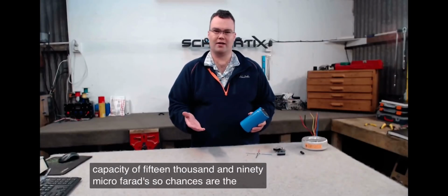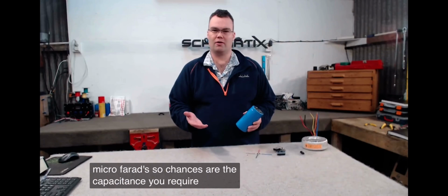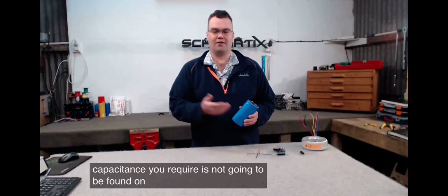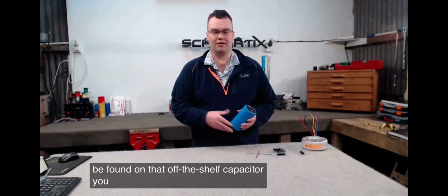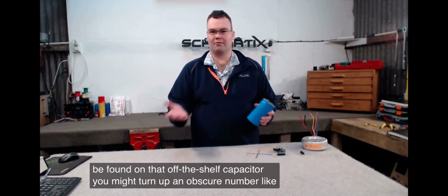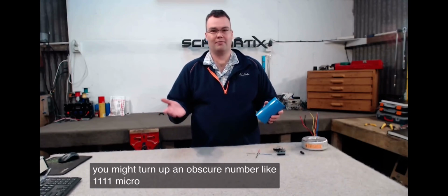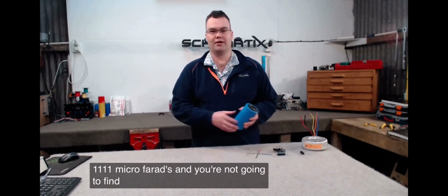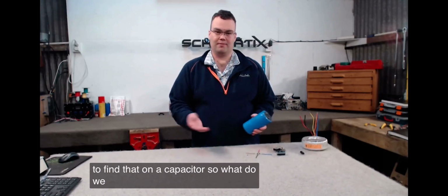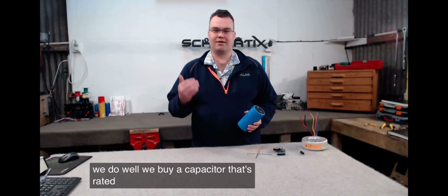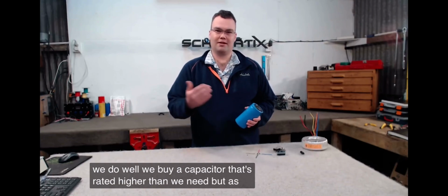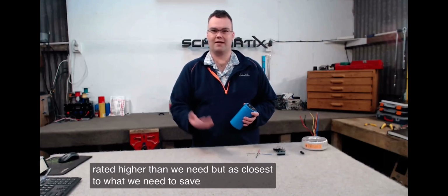So chances are the capacitance you require is not going to be found on an off-the-shelf capacitor. You might turn up an obscure number like 1,111 microfarads, and you're not going to find that on a capacitor. So what do we do? Well, we buy a capacitor that's rated higher than we need, but is closest to what we need to save on money.